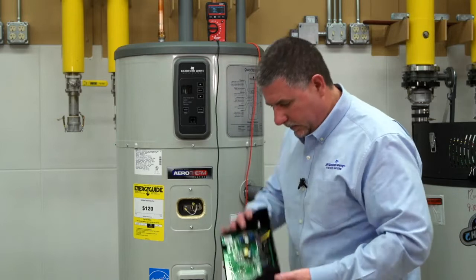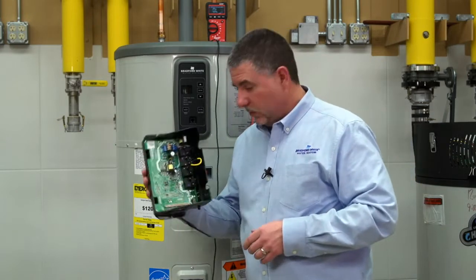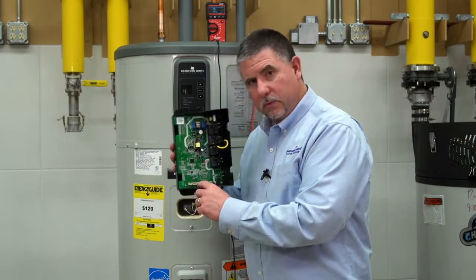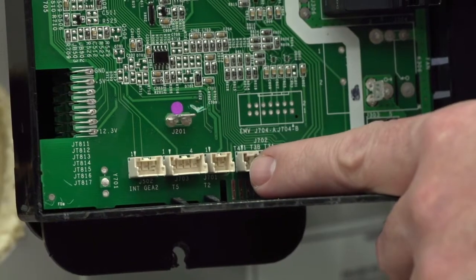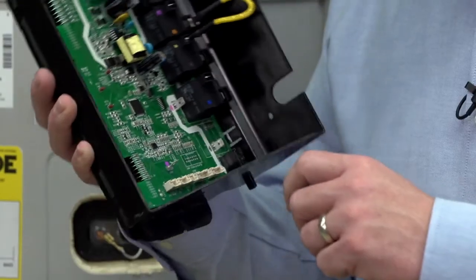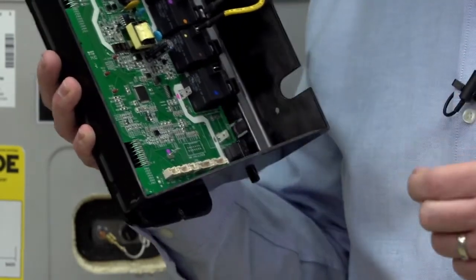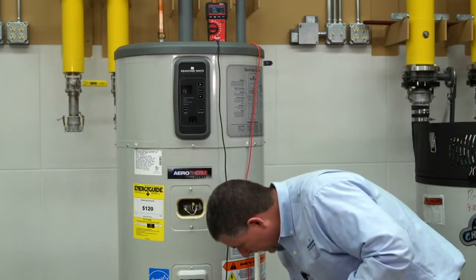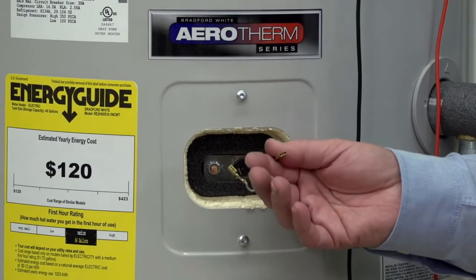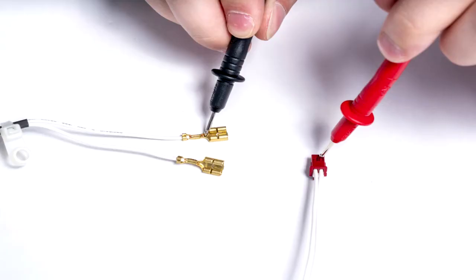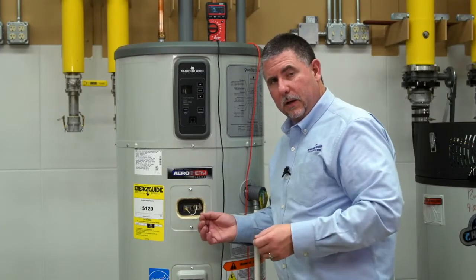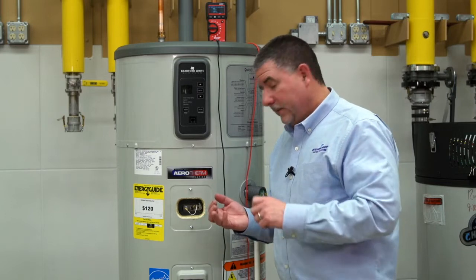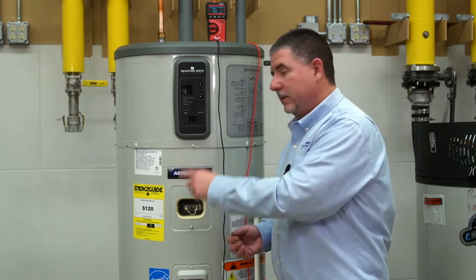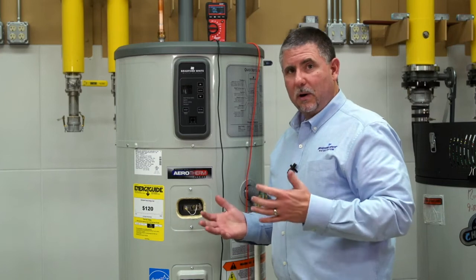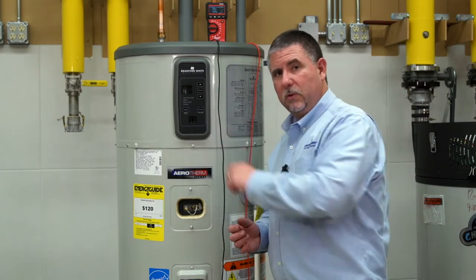So for video purpose, I've actually removed the control to show you the T2 sensor plugs into the board. It's like a burgundy connector. You unplug that T2 sensor wire. We're going to measure continuity from one wire to the appropriate end or connection going onto the board. So you measure continuity of both wires. So if your T2 sensor is good, if your wires have continuity from the sensor to the control, the last part that we're unable to really test would be your control board.